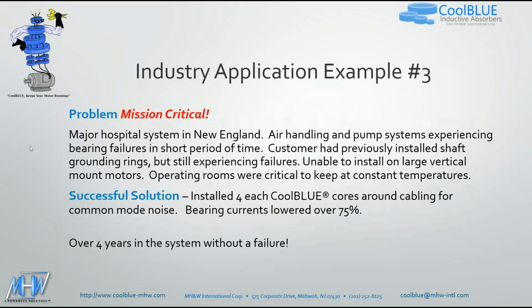Example number 3, major hospital system in New England. The air handling and pump system was experiencing bearing failures in a short period of time. The customer had previously installed shaft grounding rings, but still experienced failures. They were unable to install them on large vertical mount motors. The operating rooms were critical to keep at a constant temperature. The solution: they installed 4 CoolBLUE cores around the cabling for common mode noise. The bearing currents were lowered by over 75%. It's been now over 4 years, and the system hasn't failed.